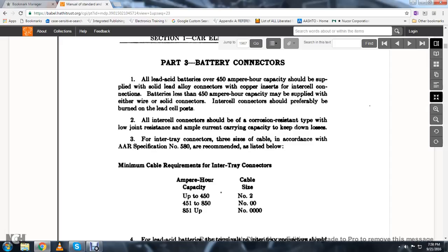Part Three, battery connectors. All lead acid batteries over 450 ampere-hour capacity should be supplied with solid lead alloy connectors with copper inserts. For inter-cell connections, batteries less than 450 ampere capacity must be applied with either wire or solid connectors. Inter-cell connectors should preferably be burned on lead cell posts. All inter-cell connectors should be of corrosion resistant type with low joint resistance and ample current carrying capacity to keep losses down.